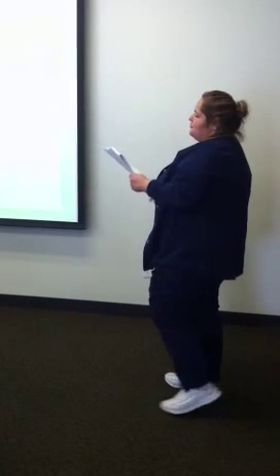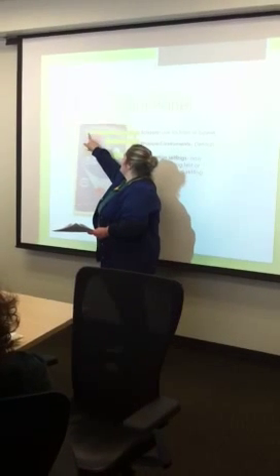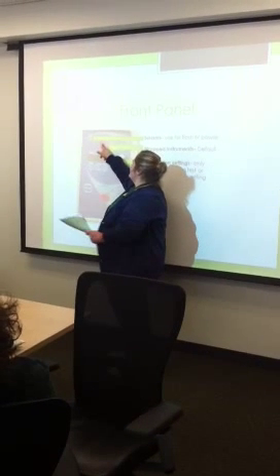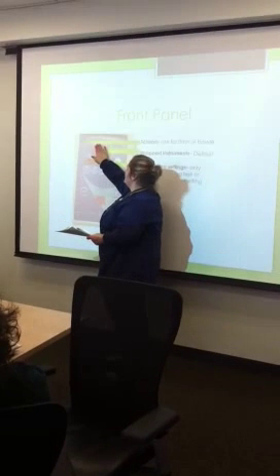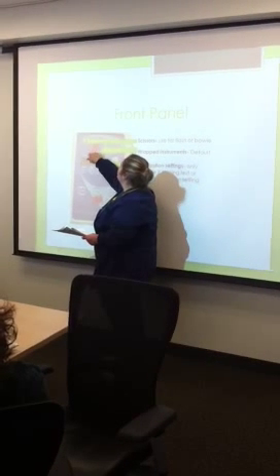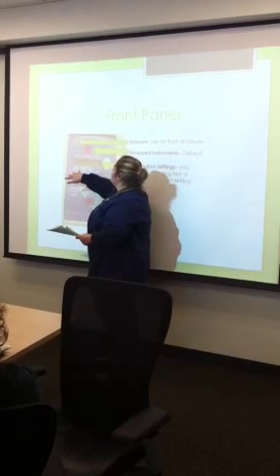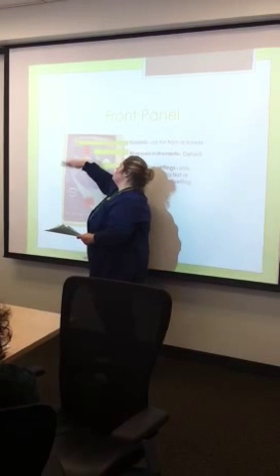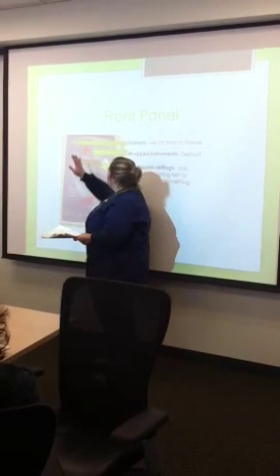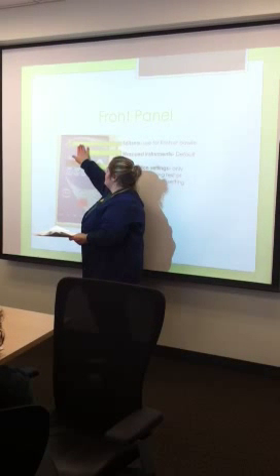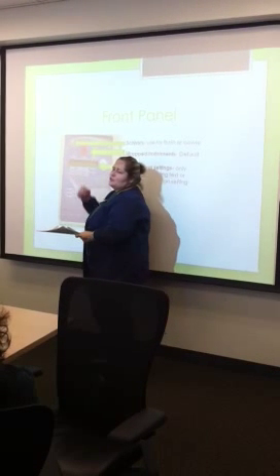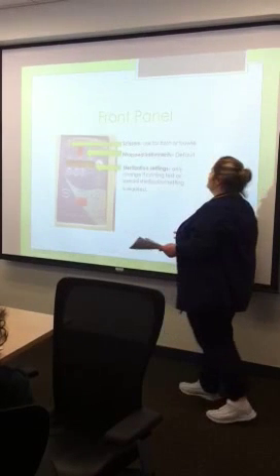So this is just showing you the front panel of the machine. So the couple of things that we use: the one that we always use here is this one. It's got a picture of a shirt on it. That's saying that it's a wrap. Anything that's wrapped is right here. If you're doing the maintenance cycle or you're flashing, say, vasectomy instruments, because you've got a really busy day, the flash cycle does the same thing as this does as far as sterilizing it, but there's no dry time. So you're saving 30 minutes.